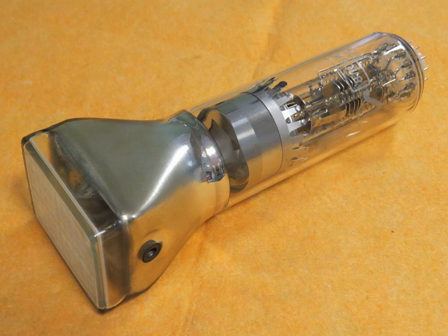Topic. Astigmatism. This control may instead be called shape or spot shape. It adjusts the voltage on the last CRT anode immediately next to the Y deflection plates. For a circular spot, the final anode must be at the same potential as both of the Y plates. For a centered spot, the Y plate voltages must be the same. If the anode is made more positive, the spot becomes elliptical in the X plane as the more negative Y plates will repel the beam.